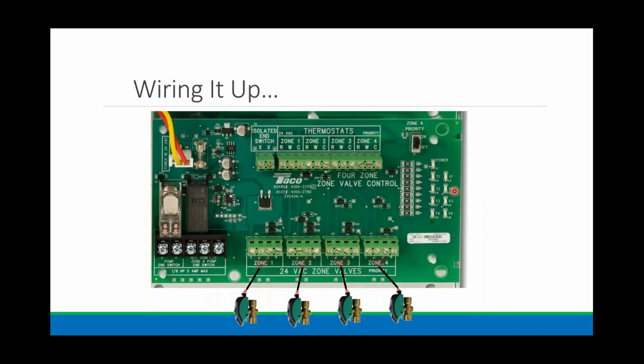Well, to make life easy for you, Taco does have our zone control relays for either zone valves or for pumps. This does make life easy. It takes a B tech in your company who maybe is a little sketchy on wiring and can really elevate them to an A tech when it comes to wiring, because this is very simple to set up. What are we going to do? Well, first off, we've got incoming power coming into this, and that's pretty obvious. All right, that's your red and orange wire there off to the side.